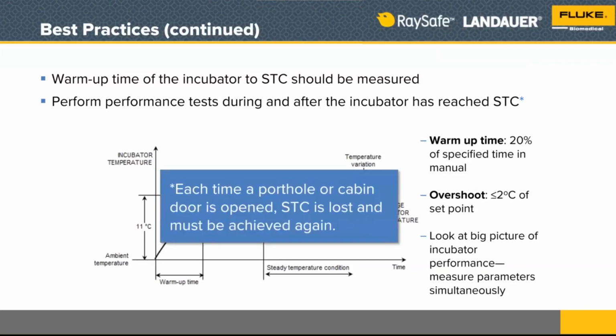Each time you open a porthole or a cabin door, the STC is lost and it has to be achieved again. So you want your measurements to be made inside the chamber. You don't want to be opening the door to move your temperature measurement sensor, which is why we designed our infant incubator analyzer the way that we did. So you set it up once, it's inside the chamber, you're able to run all your tests, and it's not necessary to open that door or any of the portholes.